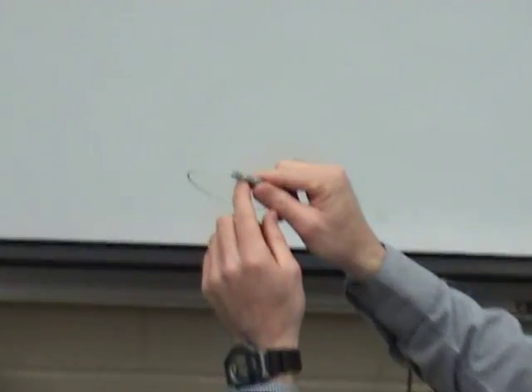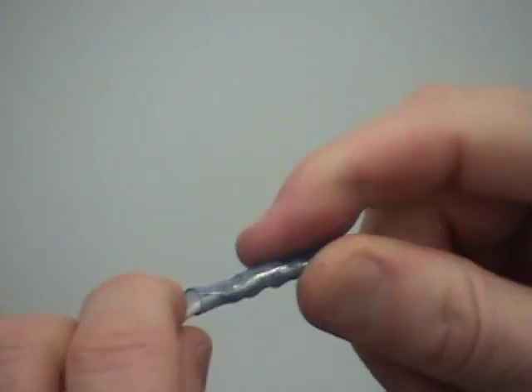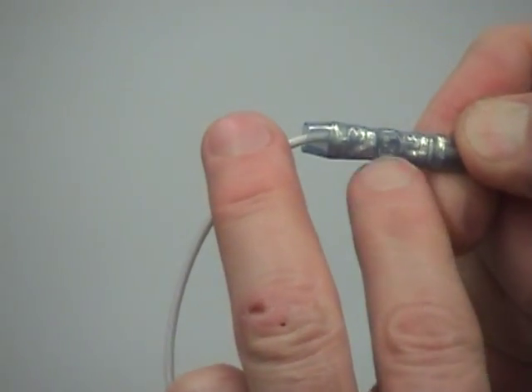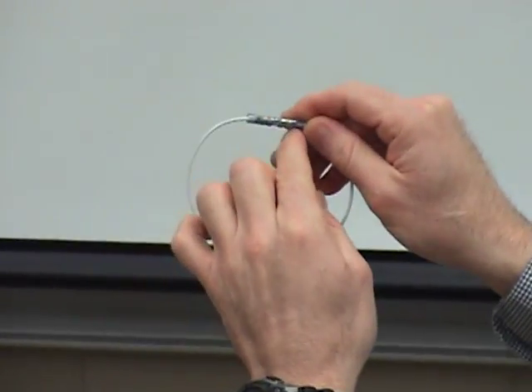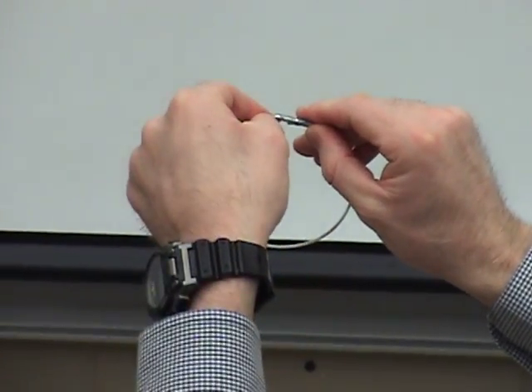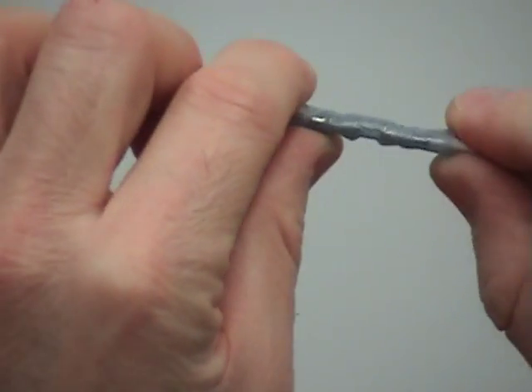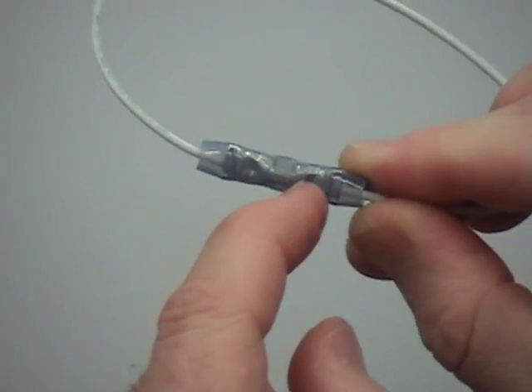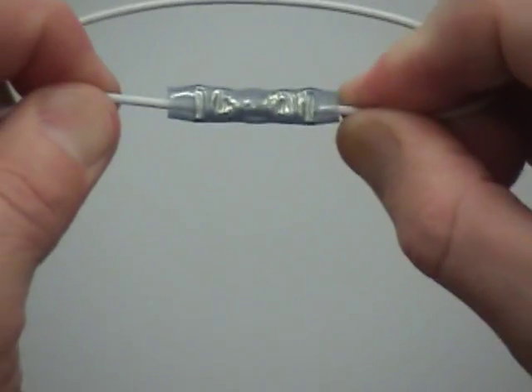Then I'm going to inspect it. Same deal. I want to see the two crimps. One on the bare wire. One on the insulation. I can see the wire protruding through the window. I need to see that bare wire. And then finally the tug test. And they're in line. I didn't crimp here on this end and then crimp sideways. You want the two crimps to be perfectly in line. And I should see four indentations. One, two, three, four indentations. And that is your pre-insulated crimp.